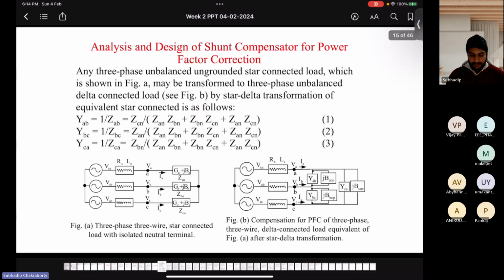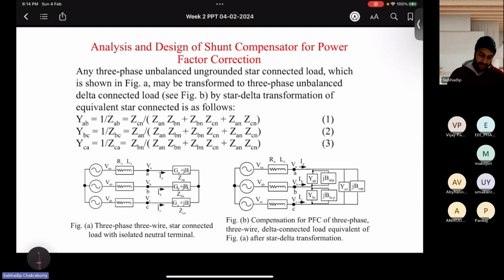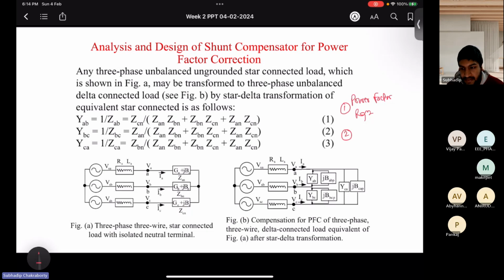So now moving on to the three-phase, three-wire system. What do we want? We want power factor regulation. But power factor regulation and zero voltage regulation at the source side are not possible simultaneously. Hope you understand that. Because once you are pushing more reactive power to correct the voltages, then maintaining unity power factor is not possible. Hope it is clear. So either you want to regulate the power factor at the source end or the voltage. Either of the two is possible, but not both simultaneously.